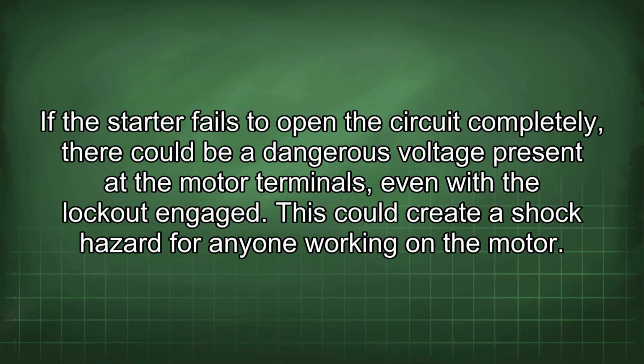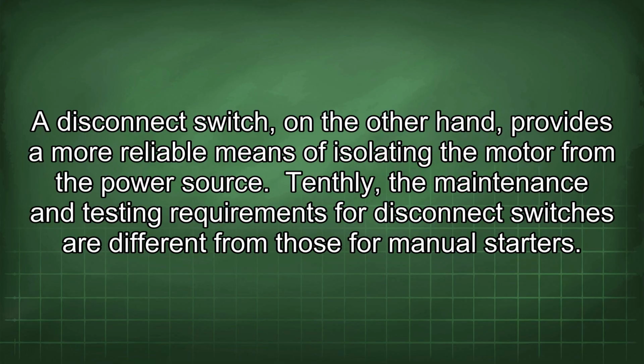If the starter fails to open the circuit completely, there could be a dangerous voltage present at the motor terminals, even with the lockout engaged. This could create a shock hazard for anyone working on the motor. A disconnect switch, on the other hand, provides a more reliable means of isolating the motor from the power source.